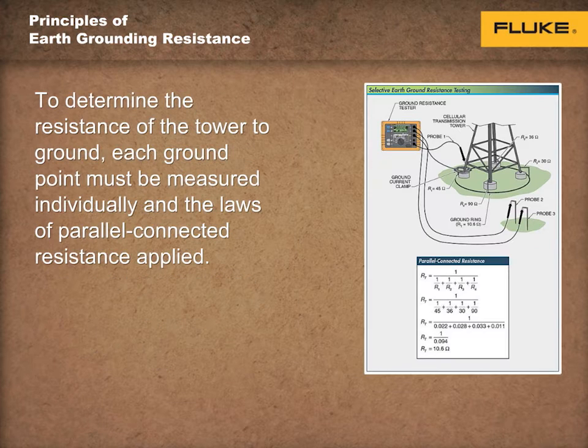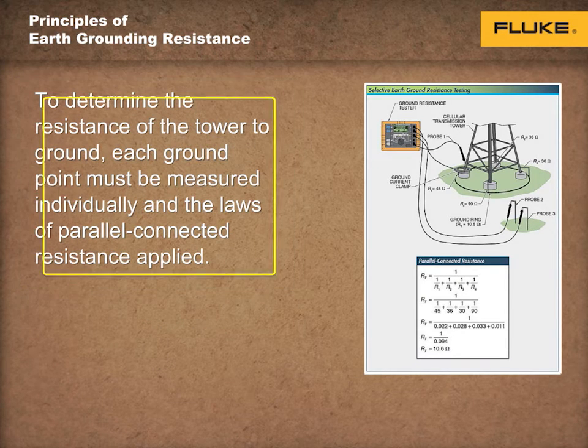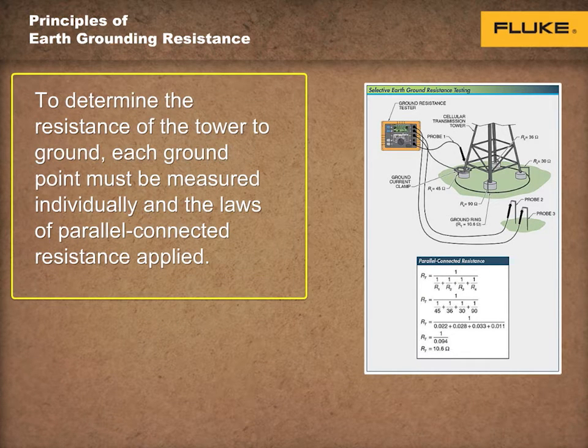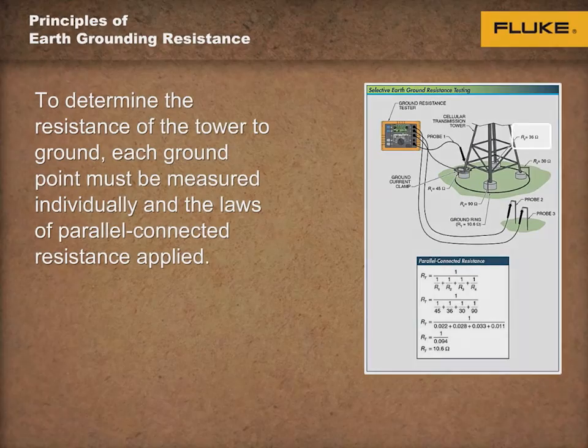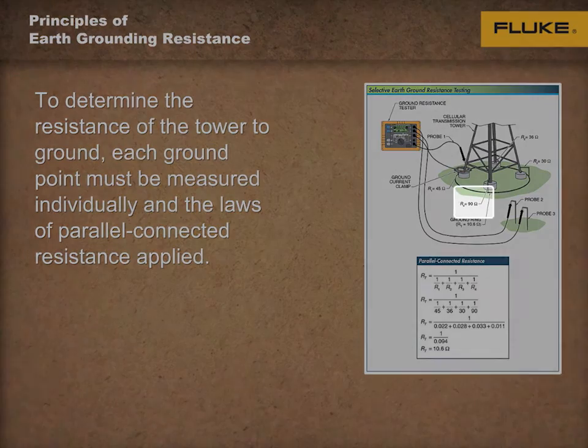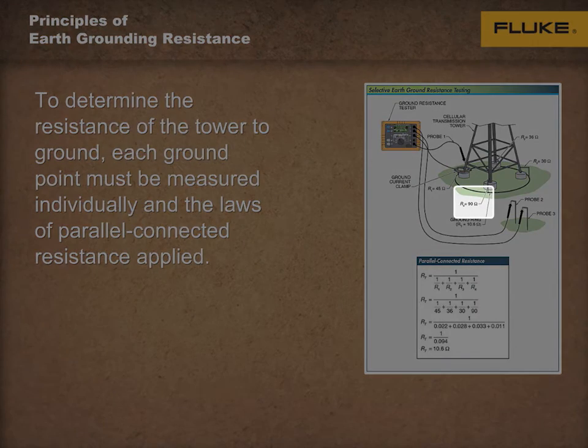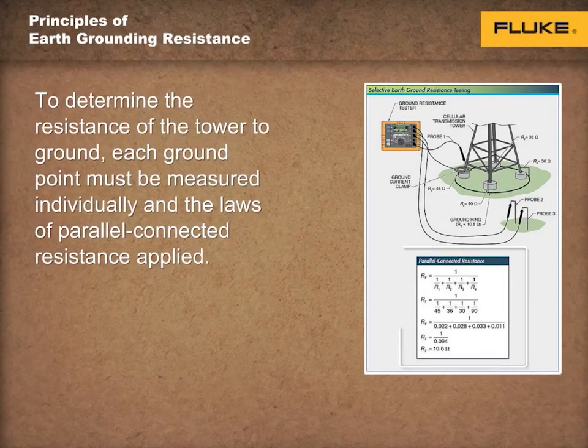To determine the resistance of the tower to ground, each ground point must be measured individually, and the laws of parallel connected resistance are applied. As shown on the screen, for example, if the measured resistances of the four test points — tower leg ground — are approximately 45 ohms, 36 ohms, 30 ohms, and 90 ohms, the effective resistance of the total ground system is 10.6 ohms.